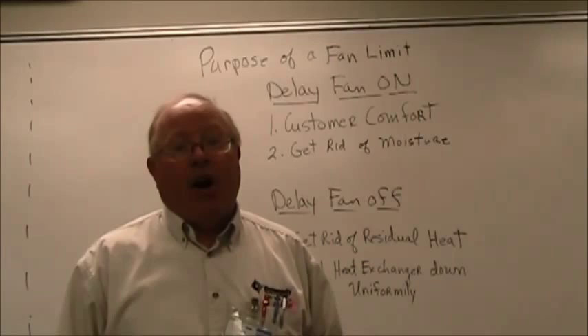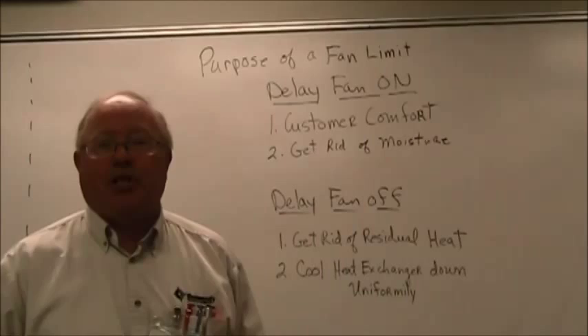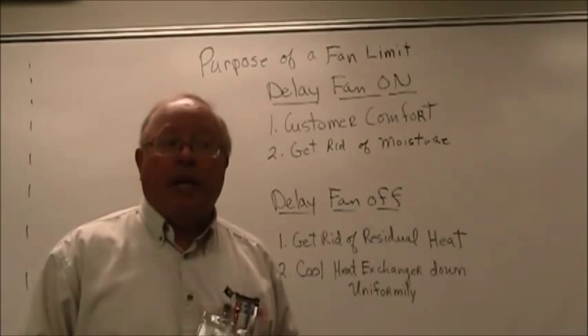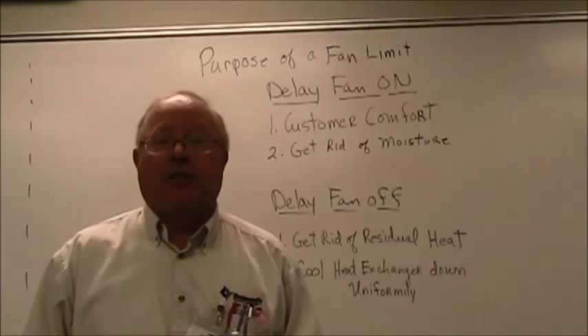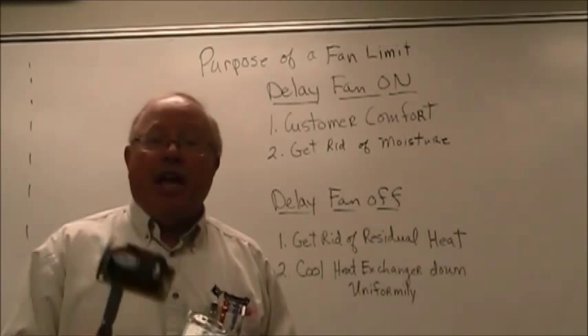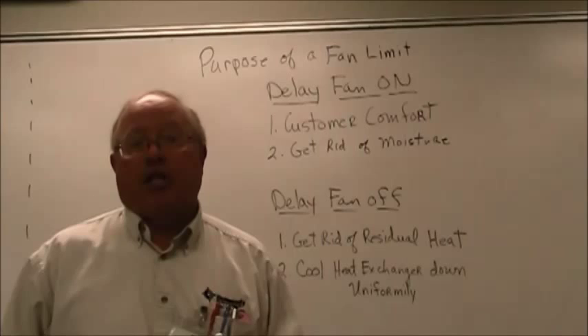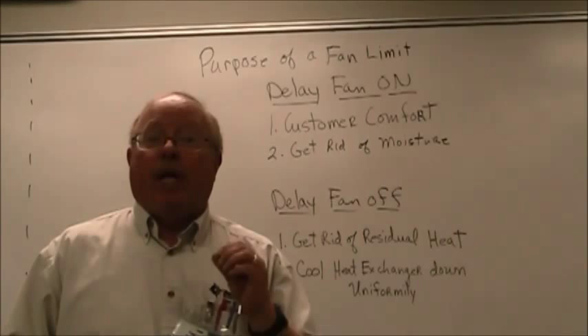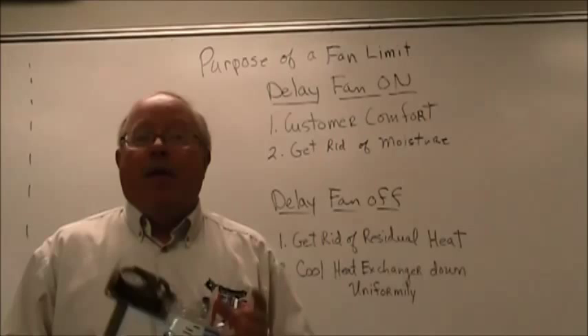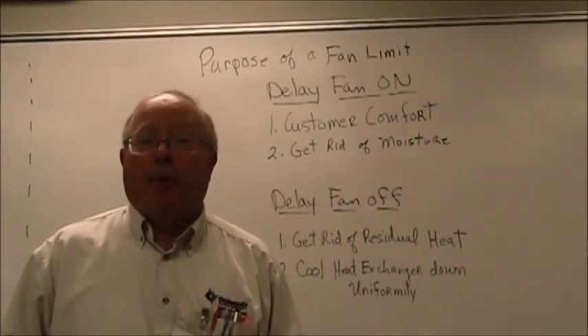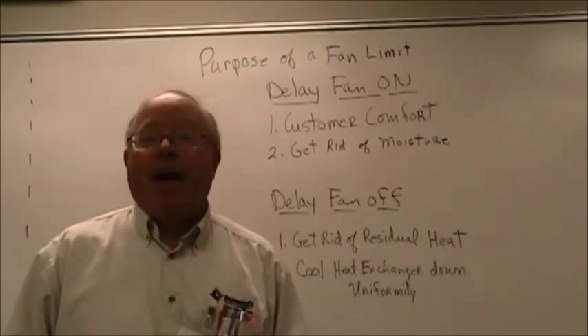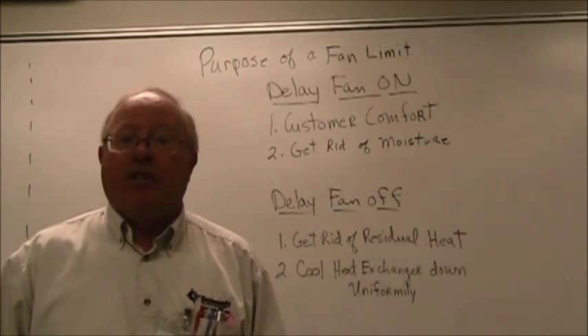The second reason for delaying the fan on is to get rid of moisture. When the products of combustion come in contact with a cold heat exchanger, those products of combustion have steam in them, and that steam is going to condensate and form water or moisture on the inside of the heat exchanger. If that water stays there for any length of time, it's eventually going to corrode the heat exchanger, causing pinhole leaks and eventually the demise of the heat exchanger. If we let the burner run for a little while before we turn the fan on, that will allow the flames to re-evaporate any steam that has condensated on the inside of the heat exchanger. Once that moisture is gone, we can let the fan turn on and start sending heat into the house.